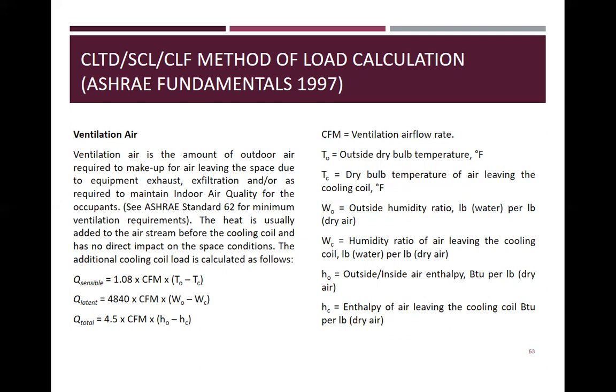Q sensible is 1.08 times CFM times T sub O minus T sub C. Q latent is 4840 times CFM times W sub O minus W sub C. Q total is 4.5 times CFM times H sub O minus H sub C. CFM is the ventilation airflow rate. T sub O is the outside dry bulb temperature. T sub C is the dry bulb temperature of air leaving the cooling coil. W sub O is the outside humidity ratio. W sub C is the humidity ratio of air leaving the coil.